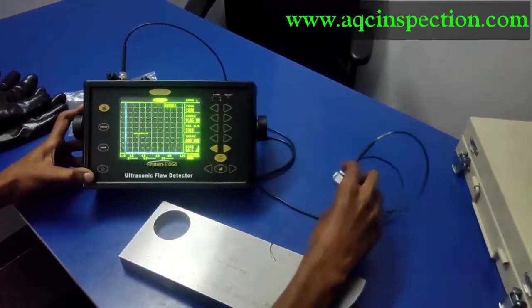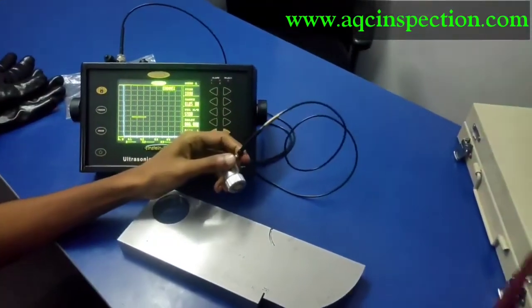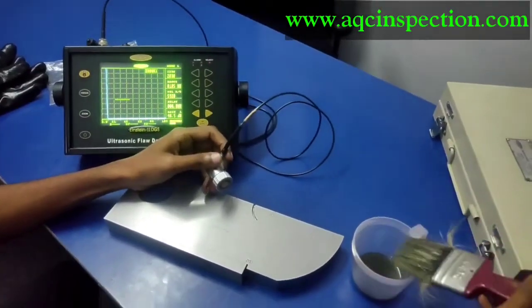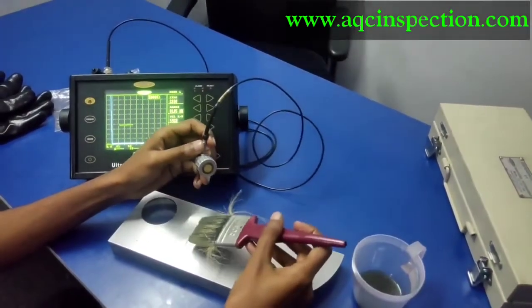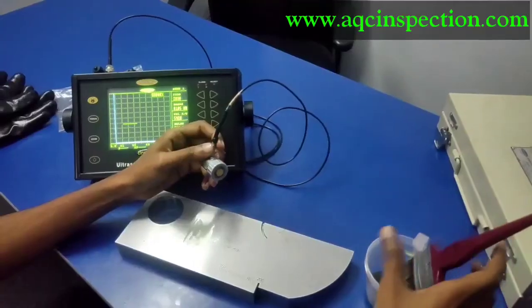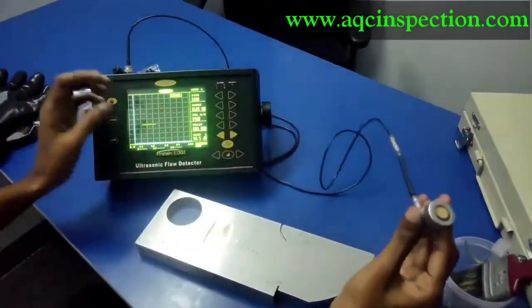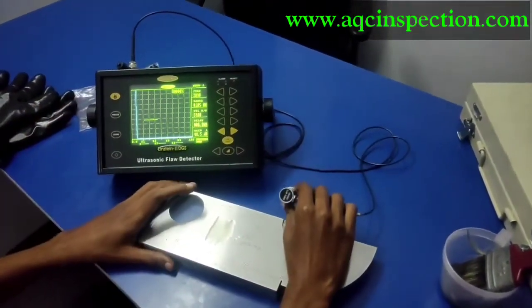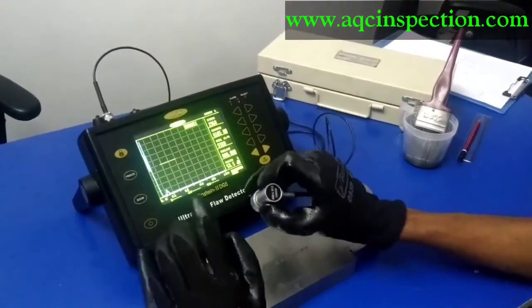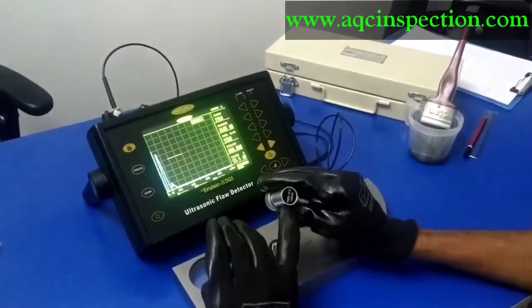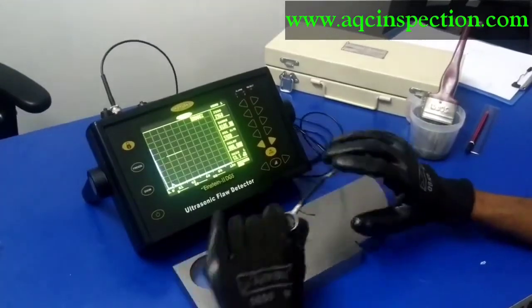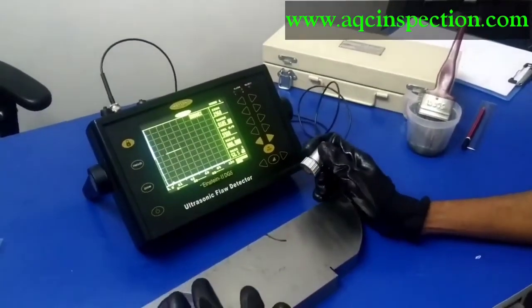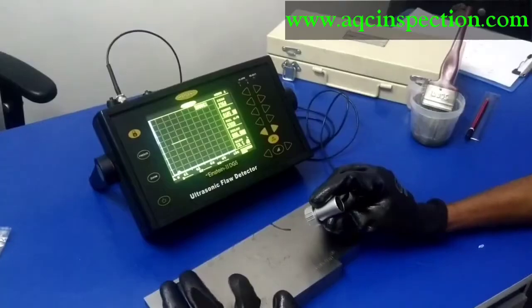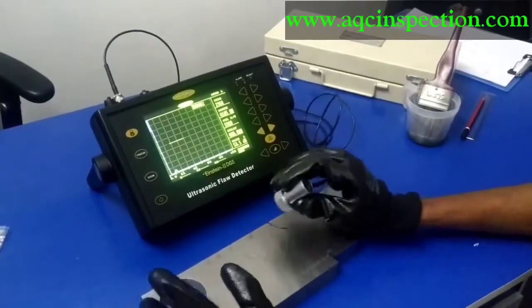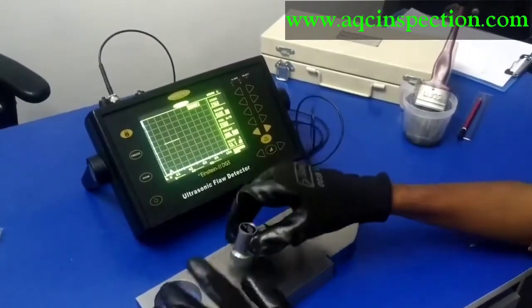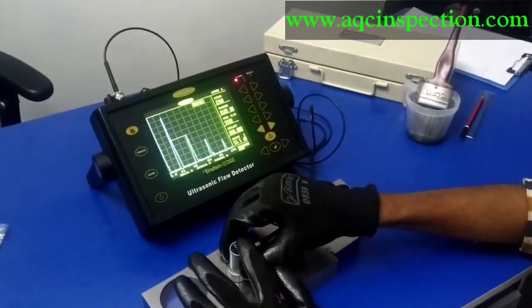Let's start. Okay. First we have to put a couplant. I am going to use oil only, just 2T oil, normal motor oil. You can use water, glycerin, anything. Now we are going to calibrate the 10 mm diameter crystal, 4 MHz frequency transducer using the V1 block right here. I have already applied the couplant. I have put oil, 2T oil, motor oil. So first what I am going to do is place the probe on the V1 block.